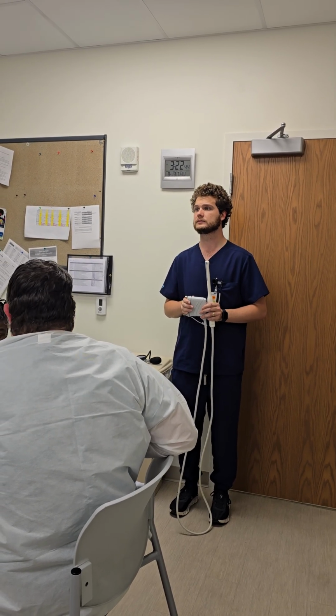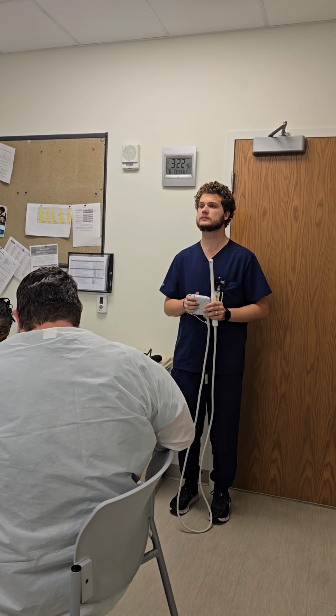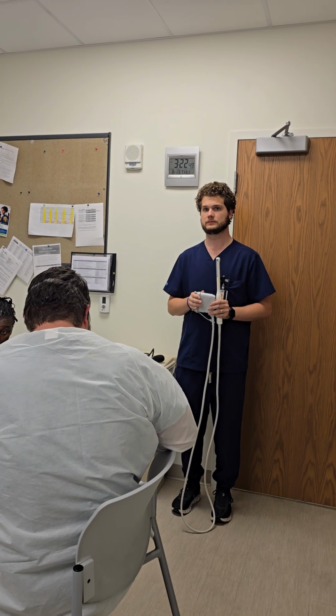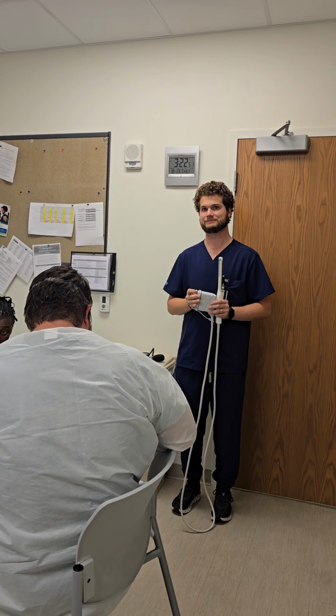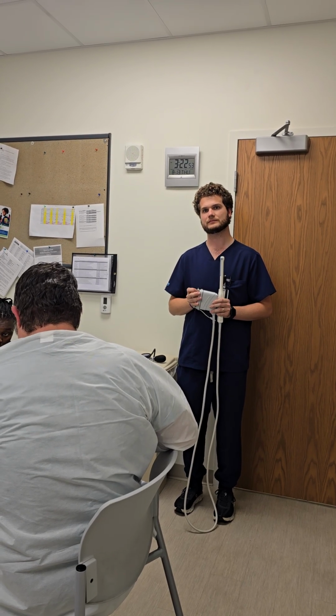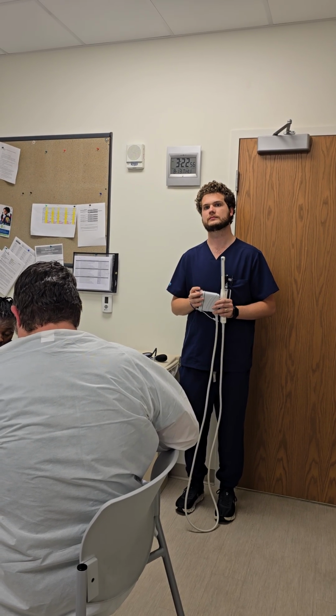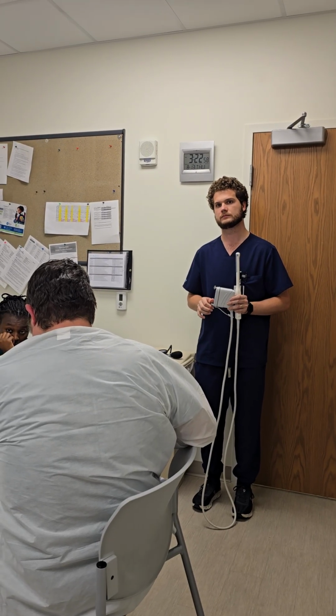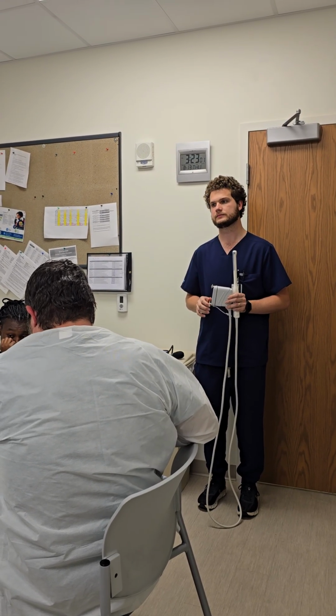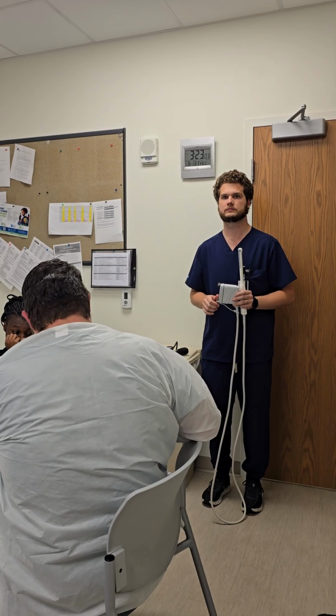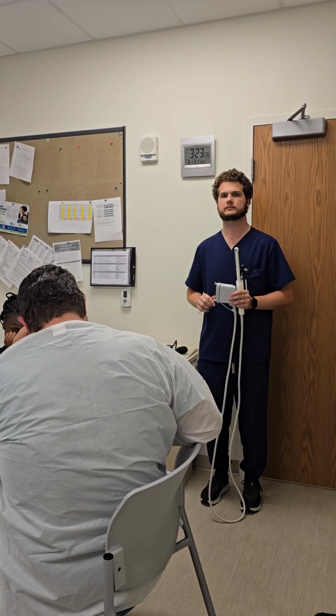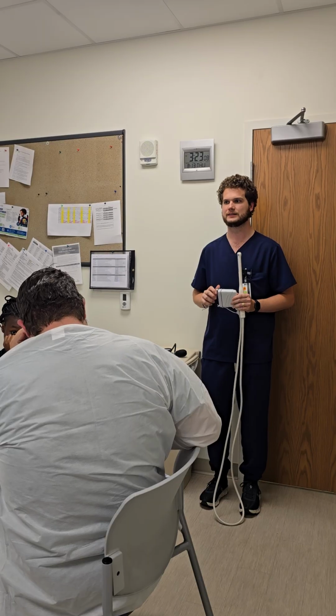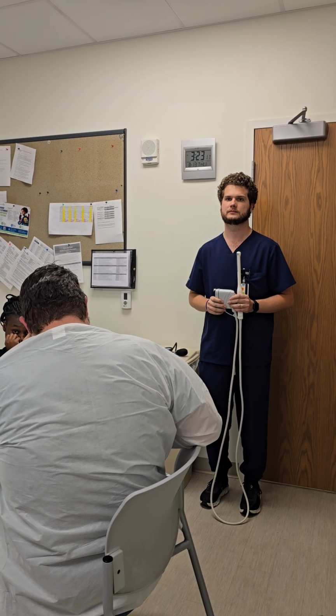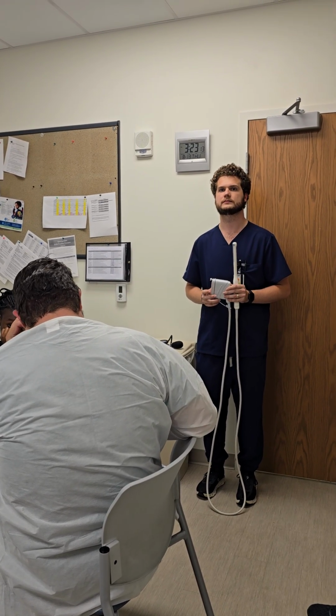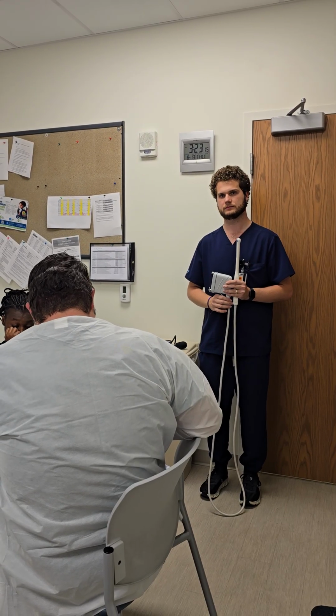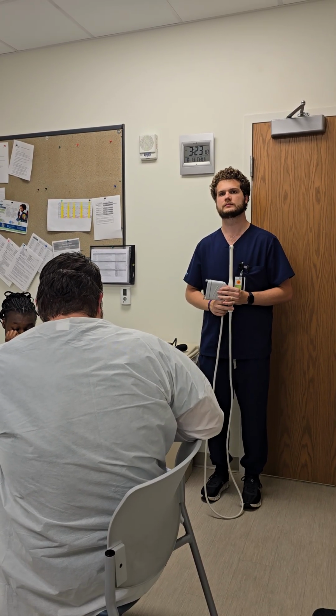What if it comes back from the OR not with the cap on and sprayed inside? When that happens, we're going to immediately escalate our point of use and let people know in the room that the cap has to be on because they shouldn't be spraying inside of that component. However, we are going to do the best of our ability to gently wipe away any of that spray. When I say wipe, it does not mean a wet wipe. You will take a dry towel, wipe out as much of that excess as you can, and then go forward with your testing. So once you test, if it did affect anything, any of those components on the inside, it will fail the test.